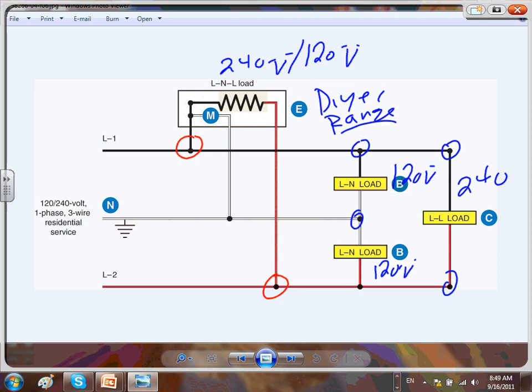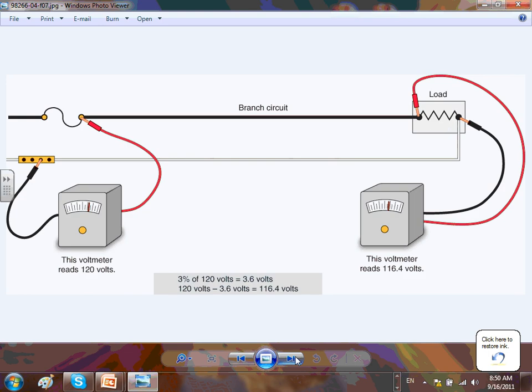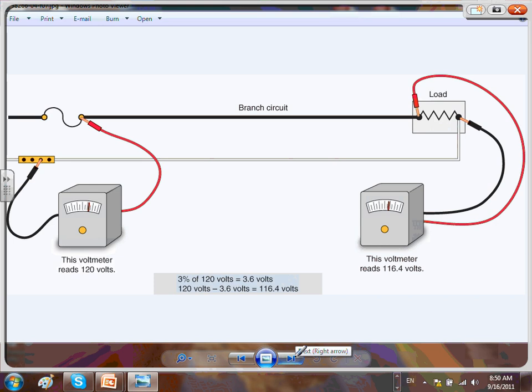This picture summarizes basically everything we do in residential. When we go to commercial, it gets more interesting because you have three types of loads you can connect: line to neutral, two-phase, or three-phase. If I have a 208/120 system, I can connect 120, three-phase, or two phases out of the three. We'll get into that when we reach it. Now, this is just a quick summary — we will do voltage drop calculation.